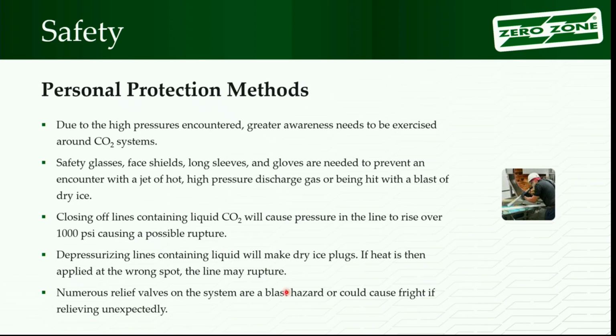Other thing you have to be aware of in working with CO2, and a lot of the other talks have been talking about it, I'm sure: if you trap CO2 liquid in a line, the pressure rises really fast. As it warms up, it can get high enough that you could easily break the line or cause the lines to swell. So when you're working with CO2, you do not want to have a liquid line, shut valves on it and trap liquid between them. If you have a filter dryer, it's full of liquid, that's what it's supposed to be. You don't want to close the valves and then walk off and do something else. It's not going to turn out well. You might have something broken. So that's something technicians need to be aware of. We don't want to bottle that up.